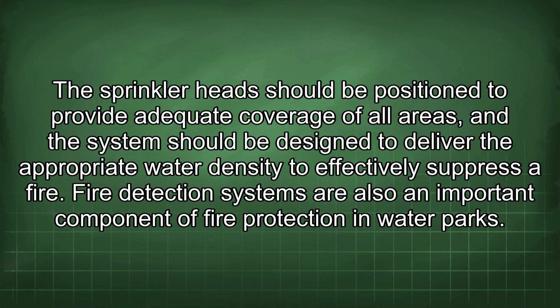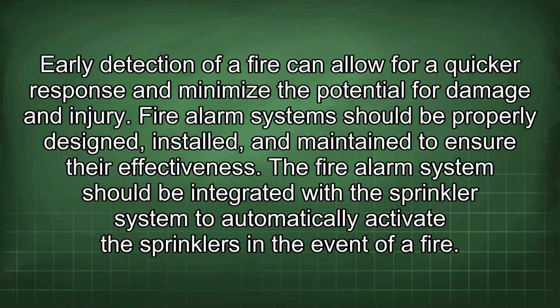Fire detection systems are also an important component of fire protection in water parks. Early detection of a fire can allow for a quicker response and minimize the potential for damage and injury. Fire alarm systems should be properly designed, installed, and maintained to ensure their effectiveness. The fire alarm system should be integrated with the sprinkler system to automatically activate the sprinklers in the event of a fire.